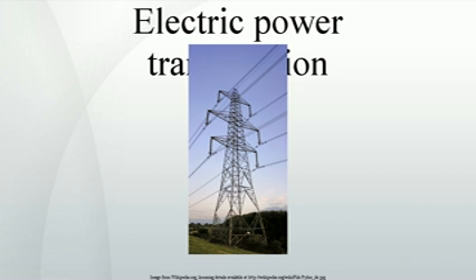In distributed power generation, the generators are geographically distributed and the process to bring them online and offline must be carefully controlled. The load control signals can either be sent on separate lines or on the power lines themselves. Voltage and frequency can be used as signaling mechanisms to balance the loads. In voltage signaling, the variation of voltage is used to increase generation. The power added by any system increases as the line voltage decreases. This arrangement is stable in principle. Voltage-based regulation is complex to use in mesh networks, since the individual components and set points would need to be reconfigured every time a new generator is added to the mesh.